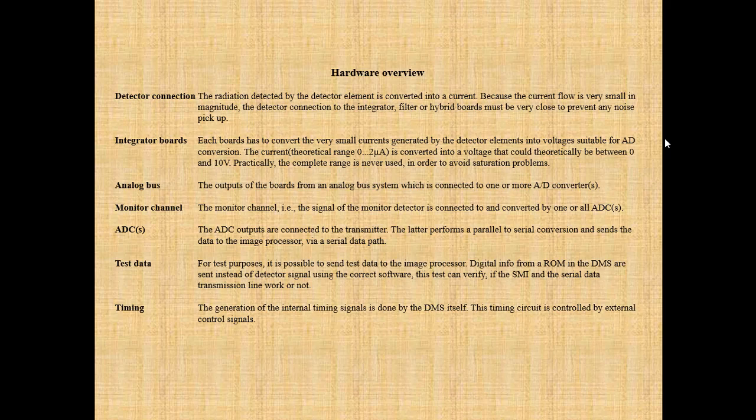Analog bus: the outputs of the integrator boards form an analog bus system connected to one or more A/D converters. Monitor channel: the signal of the monitor detector is connected to and converted by one or all ADCs. The ADC outputs are connected to the transmitter, which performs a parallel-to-serial conversion and sends the data to the image processor via a serial data path. For test purposes, it is possible to send test data — digital info from a ROM in the DMS — instead of detector signals. Using the correct software, this test can verify if the SMI and the serial data transmission line work correctly.